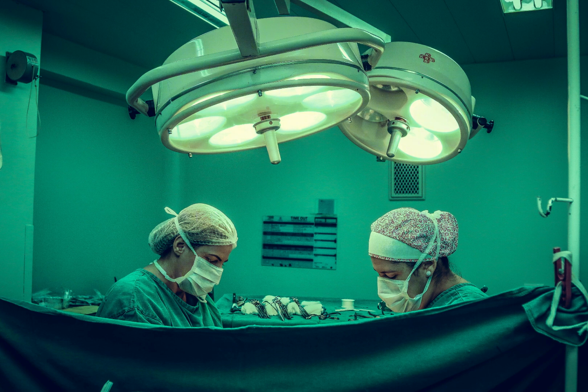So what can we, as sterile processing technicians, do with this information? Here are your key takeaways. Always inspect laparoscopic instruments before sterilization and after cleaning. Don't assume they're fine just because they passed visual inspection last time. Use an insulation tester. This is one of the easiest and most cost-effective ways to catch dangerous defects before they reach the OR. Document all failures.